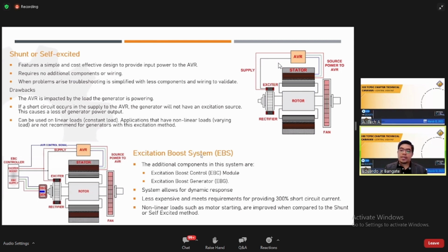Okay, but this excitation system is not recommended for continuous power application. It is intended for emergency or backup power applications, because when the generator starts, the EBS system is engaged until operating speed is reached. The EBG is still generating power, but the controller does not route it. The EBG or EBC control module is connected in parallel to the AVR and the exciter. The EBC receives a signal from the AVR. When needed, the controller supplies varying levels of excitation current to the exciter, at levels that depend on the need of the system. The additional power feed to the excitation system supports load requirements. This allows the generator to start and recover the excitation voltage.